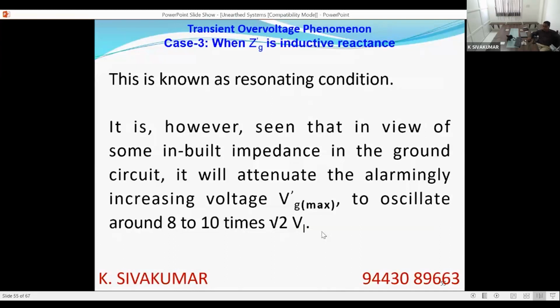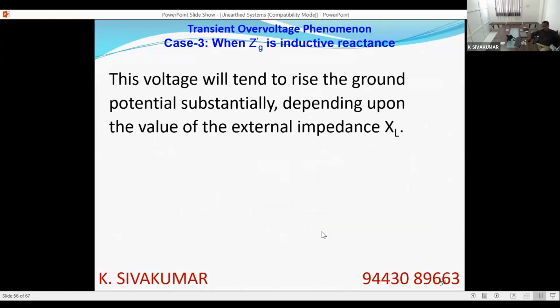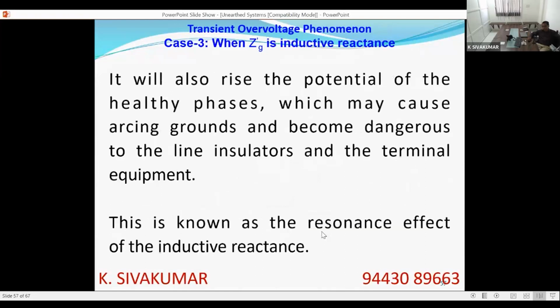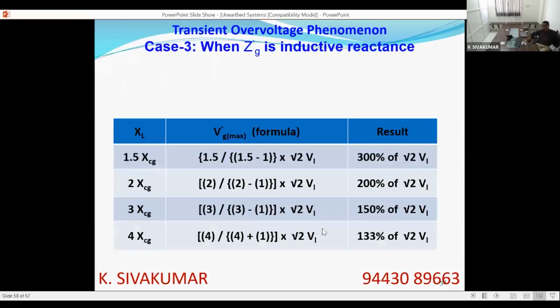This is a problem because our equipment is not designed for withstanding this voltage. So there is a chance of equipment damage and system damage. So this will tend to raise the ground potential substantially, depending upon the value of the external impedance. So it will also raise the potential of the healthy phases, which may cause arcing grounds and become dangerous to the line insulator. This is called the resonance effect.